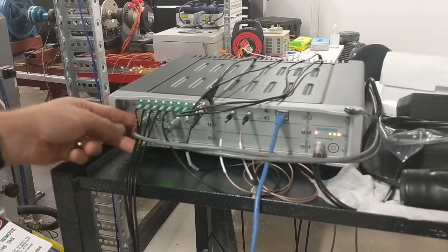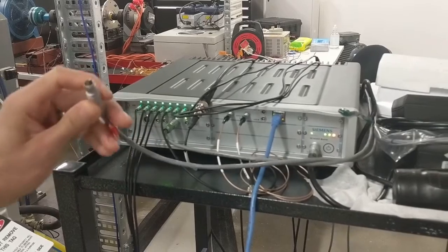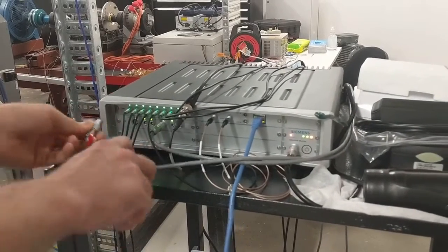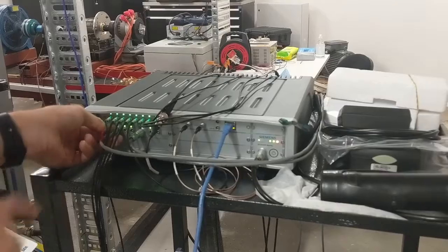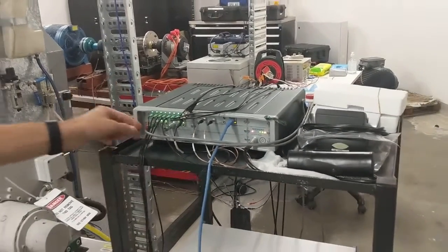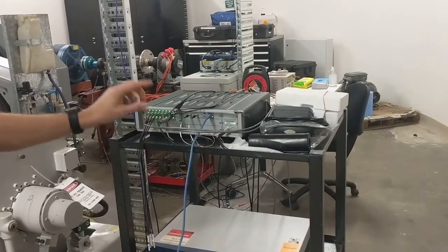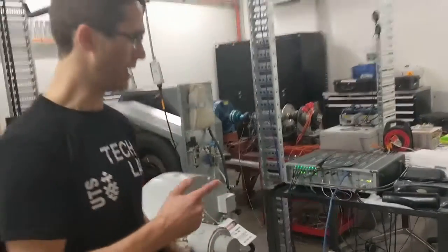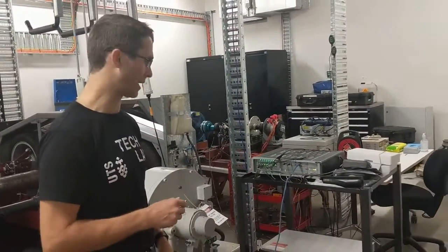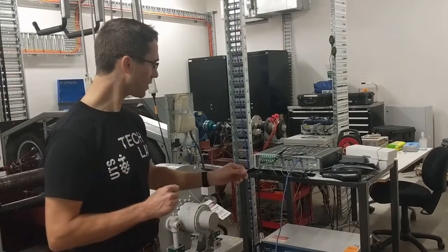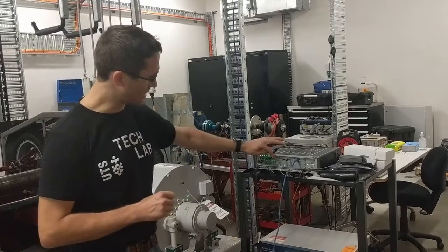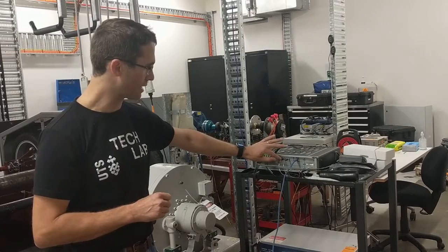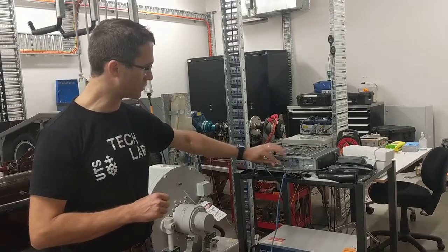The encoders are connected via these 2 connections here, which are a mil-spec connector into a separate input module which provides the power for the encoder and also allows the conversion of the various pulse train signals into rotation speed and angular position. There are some additional input channels here that are available for use, particularly a couple of tacho channels which we can use.